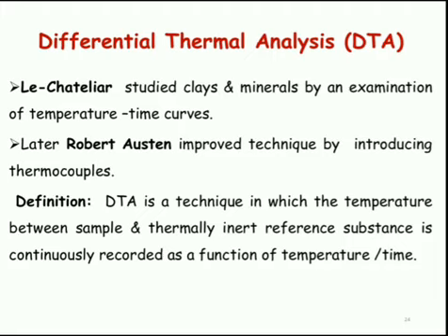Whenever the substance to be analyzed undergoes an endothermic change, like when it melts or when it is dehydrated, the temperature of the substance will be lower than that of the reference material. On the other hand, if the substance undergoes an exothermic change, its temperature will be higher than that of the reference material. When the substance does not undergo any heat change, there will be no difference in temperature between the sample and the reference material.